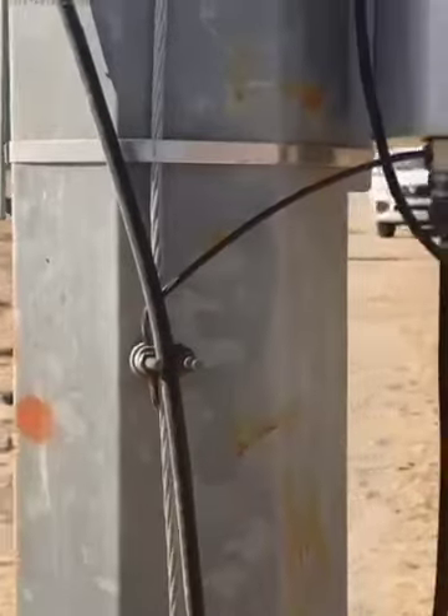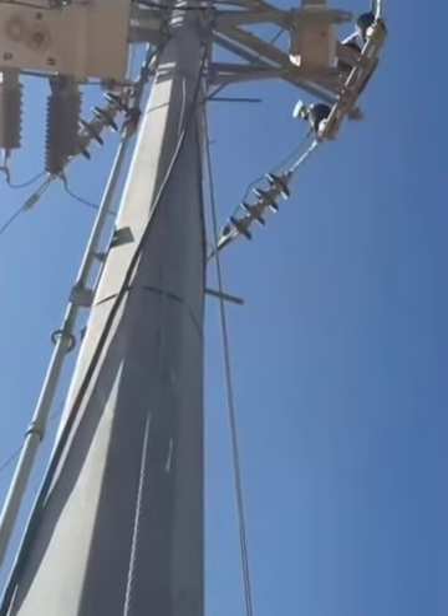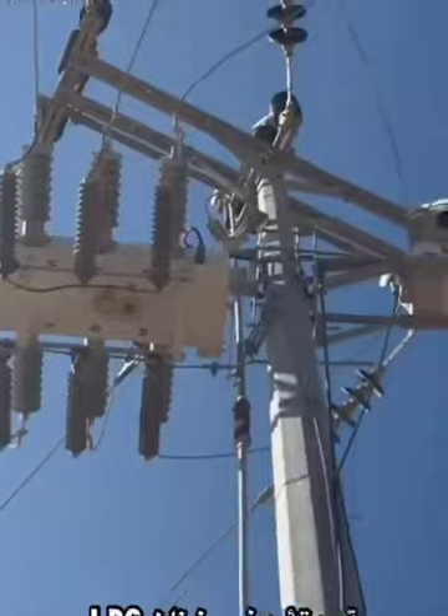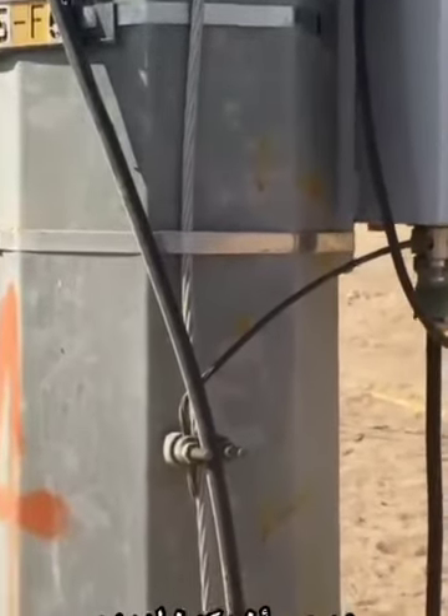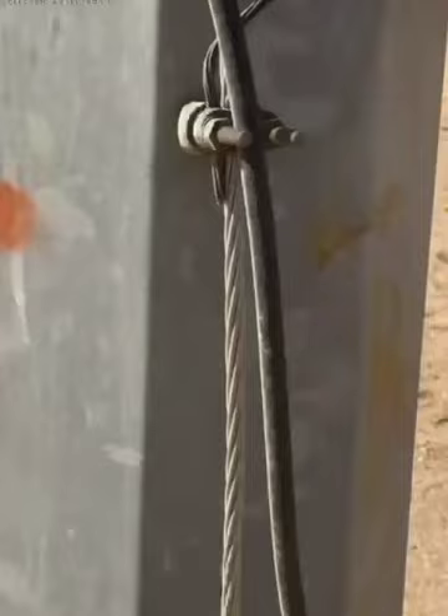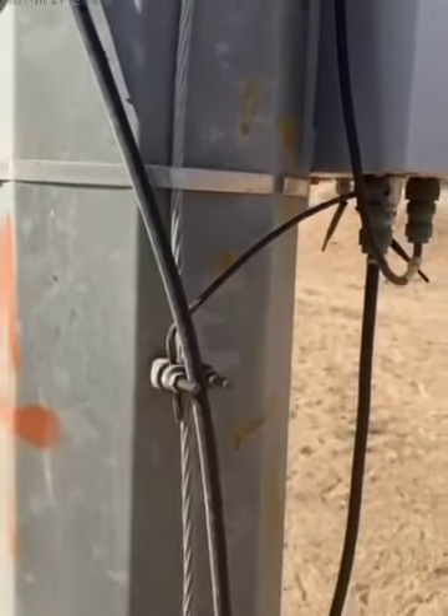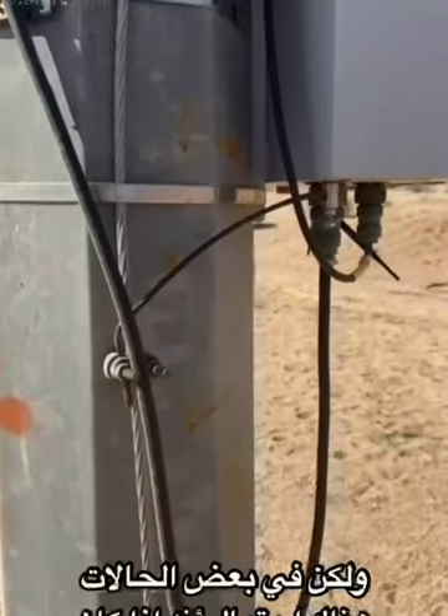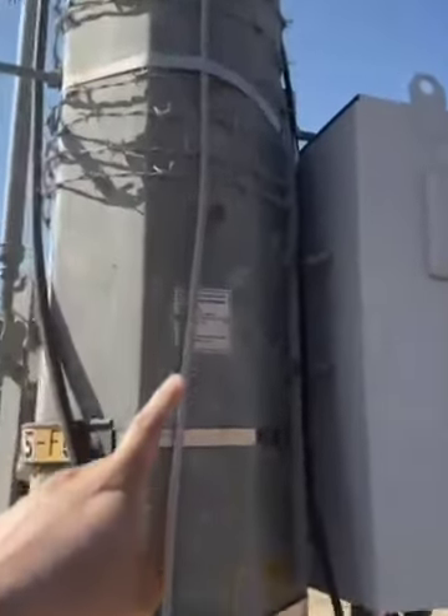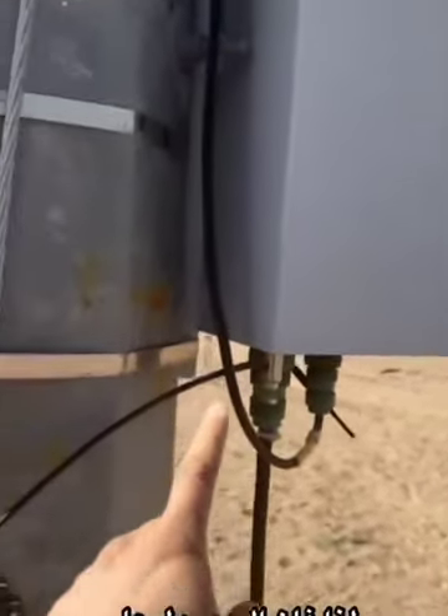Right now on this site, we can see that the earth is all combined in one line. So the controller is combined with this earth that goes to the tank. The LBS tank, the VT and the controller should actually have separate lines coming down, all earthed. But right now here it is combined. If it's combined, there could be no problems, but in some cases, if there's an external surge coming down from the tank, some of the surge can flow into the controller, damaging the controller. So it is much safer to have an individual earthing for the controller itself.